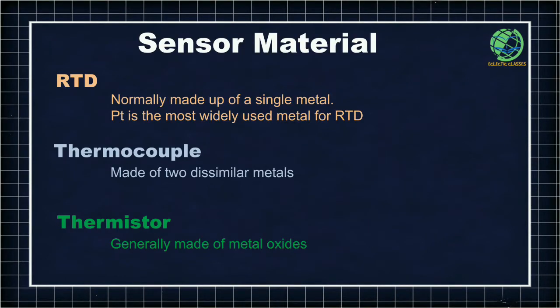In terms of sensor material, RTDs are normally made of a single metal, and platinum is the most widely used metal for RTD construction. The PT-100 is the most widely used RTD in industry. Thermocouples are made of two dissimilar metals — a junction of two dissimilar metals is essential for generation of the millivolt signal with temperature change. Thermistors are normally made of metal oxides.